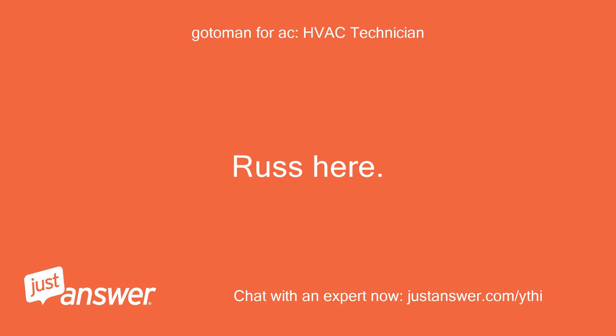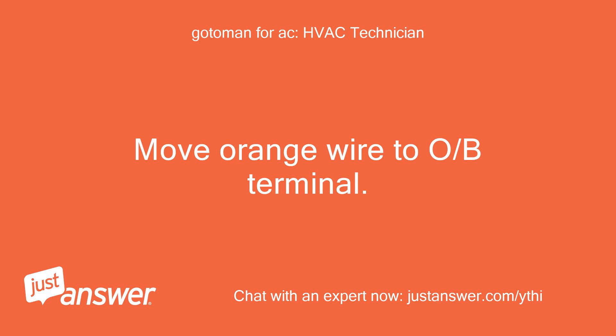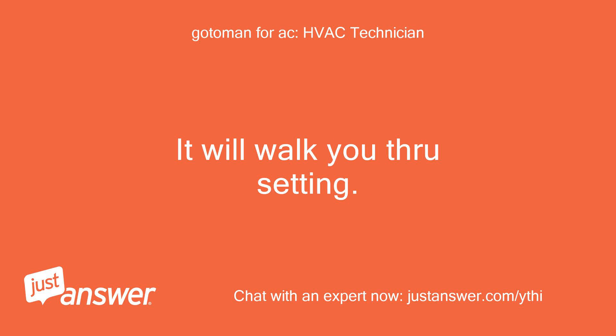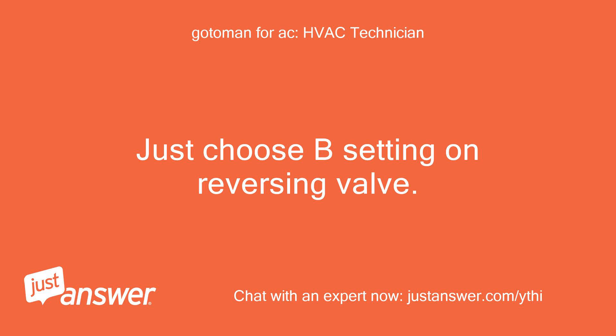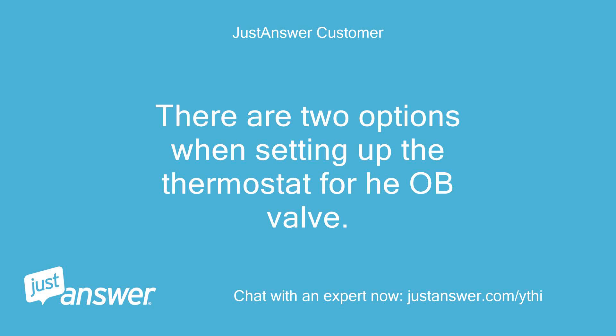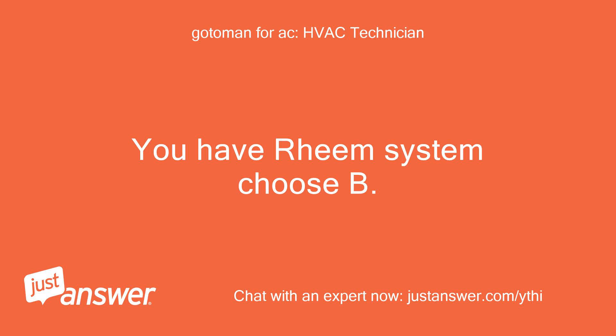Russ here. Move the orange wire to the OB terminal. When setting up the thermostat, it will walk you through the settings. Just choose the B setting on the reversing valve. There are two options when setting up the thermostat for the O/B valve. You have a Rheem system — choose B. Rheem and Weatherking are the only ones to energize in the B setting.